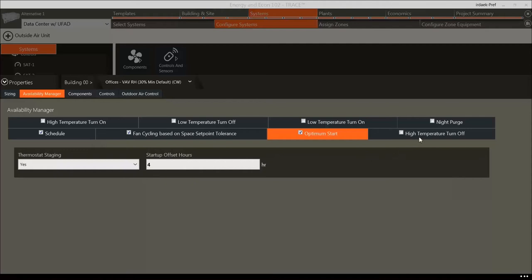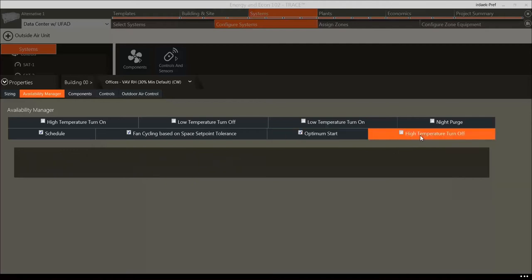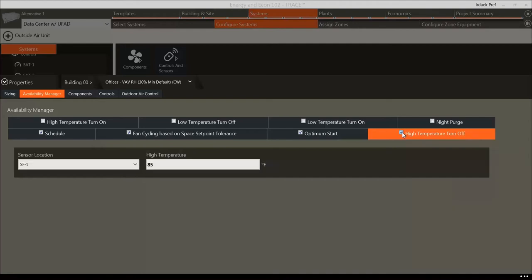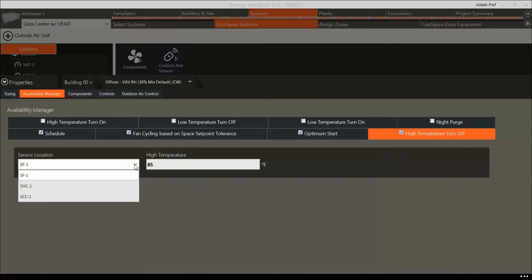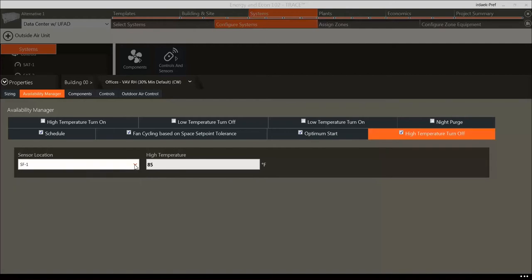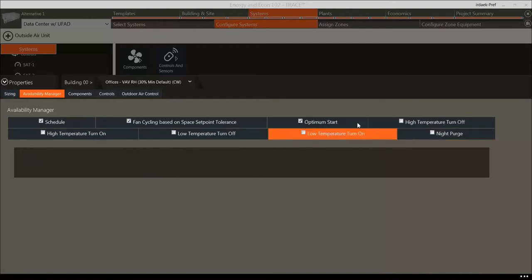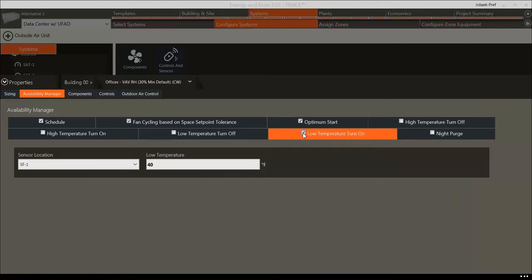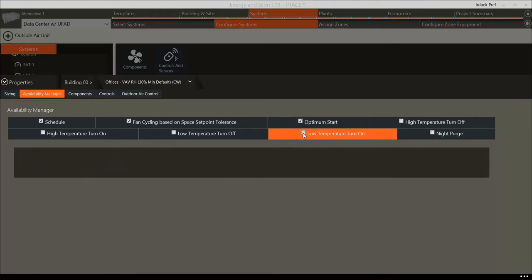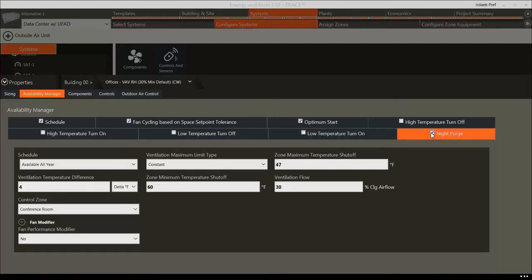Users are also able to set, enable, and disable overrides according to maximum and minimum temperatures using the High and Low Temperature Turn On and Off tabs. When the temperature limit is hit, the system will turn on or off depending on what temperature the sensor location is reading. In addition, users can configure the system to perform a nighttime air purge, which pre-cools the building during unoccupied hours by increasing the outdoor airflow.